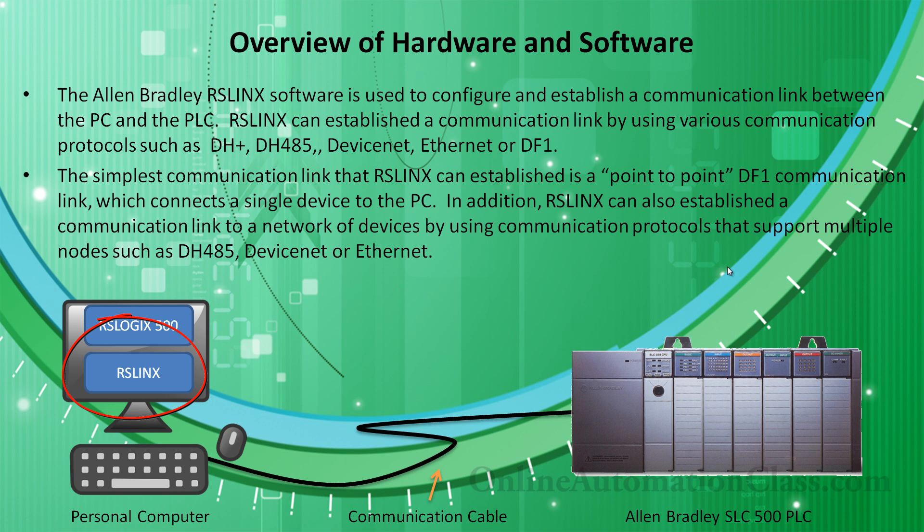The Allen-Bradley RS-Linx software is used to configure and establish a communication link between the PC and the PLC. RS-Linx can establish a communication link by using various communication protocols such as DH+, DH485, DeviceNet, Ethernet, or DF1.